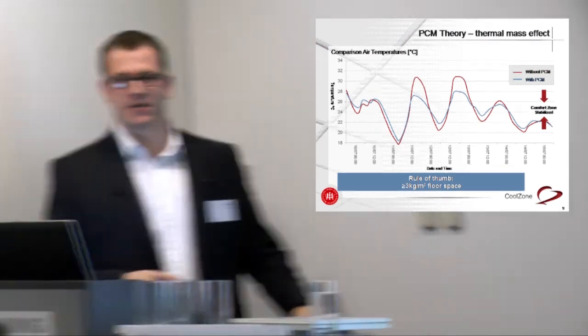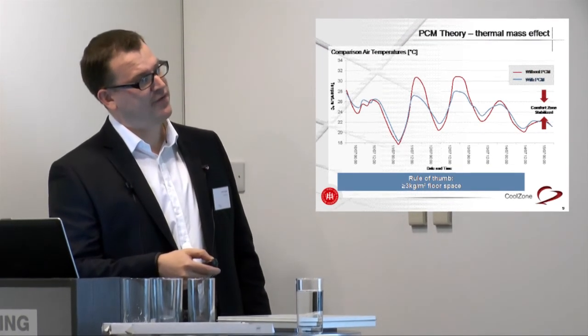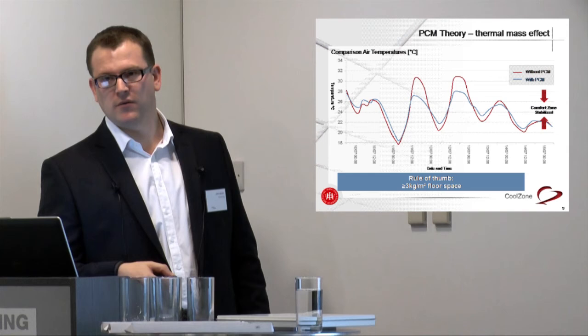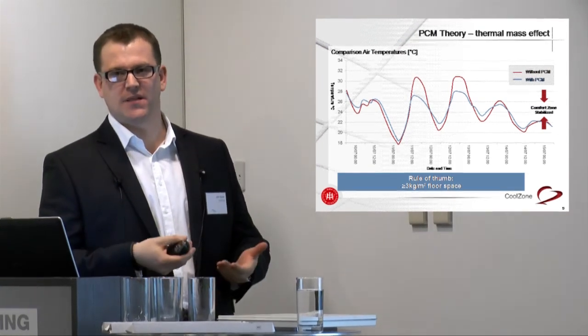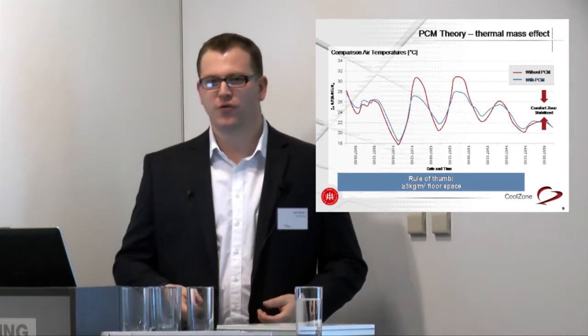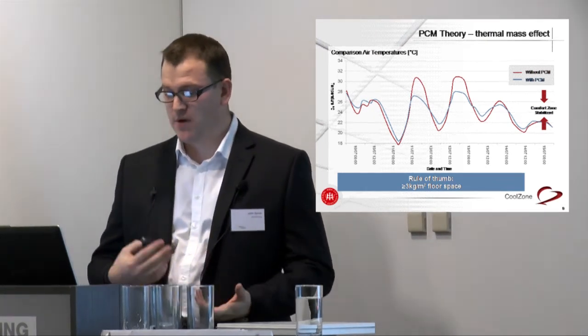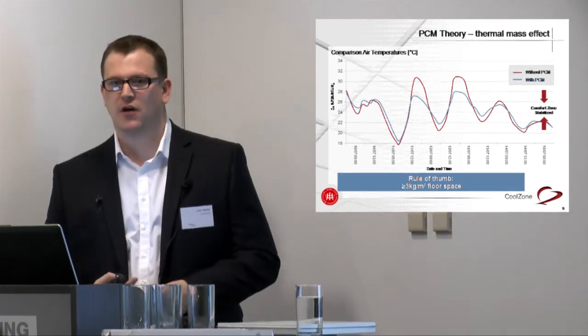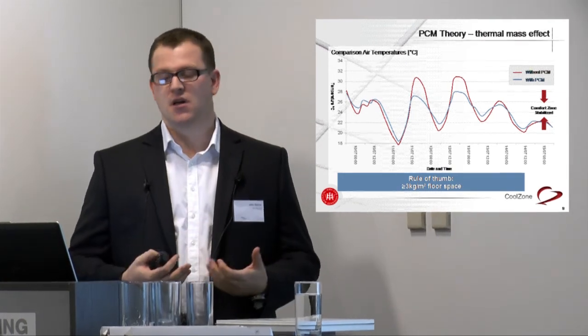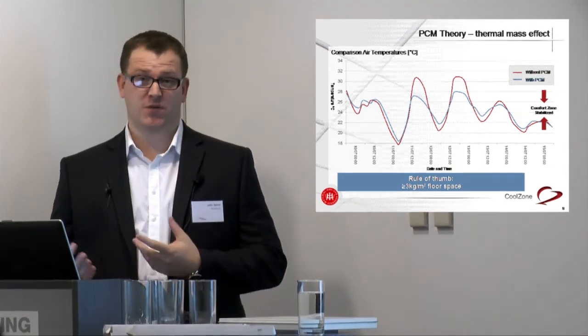And what the PCM does is chop off those peaks and cut the troughs. So we have dealt with the overheating, and then our startup temperature is slightly warmer, so you're not having to add as much heat to get the room up to temperature the next day. So we're creating this comfortable zone or a cool zone. And then the general rule of thumb is about 3 kilograms per square metre of floor space, which is about 30 to 50% of the ceiling tiles to be cool zone. The other ceiling tiles would just be an acoustical tile or your services.